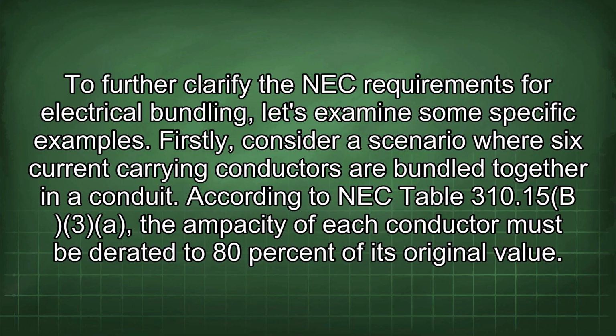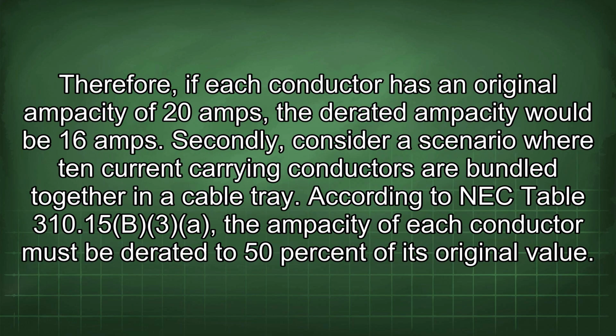Firstly, consider a scenario where 6 current-carrying conductors are bundled together in a conduit. According to NEC Table 310.15(B)(3), the ampacity of each conductor must be derated to 80% of its original value. Therefore, if each conductor has an original ampacity of 20 amps, the derated ampacity would be 16 amps.